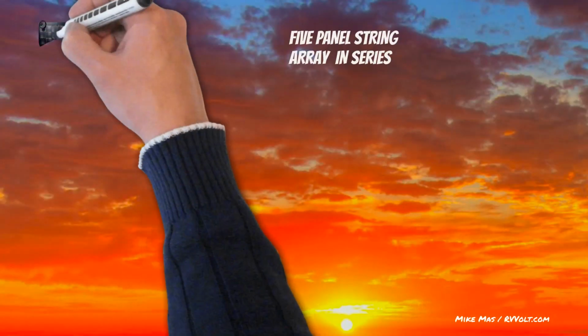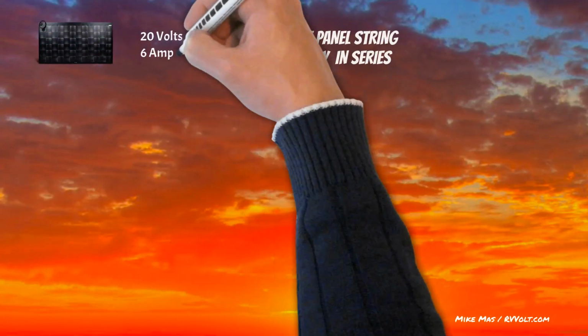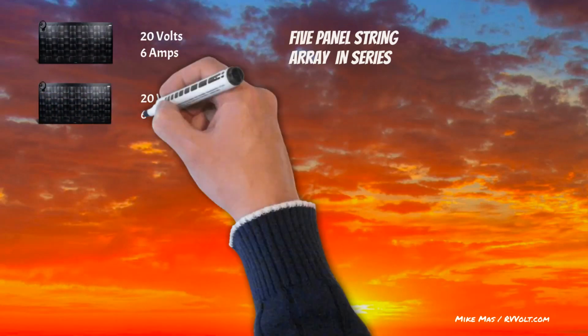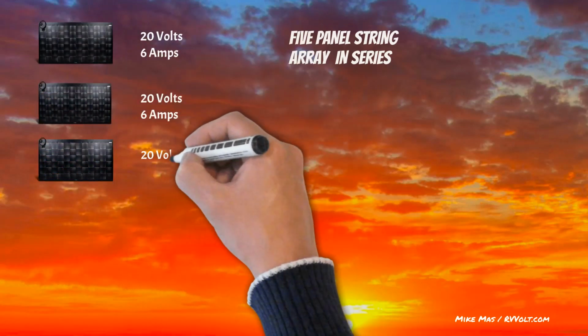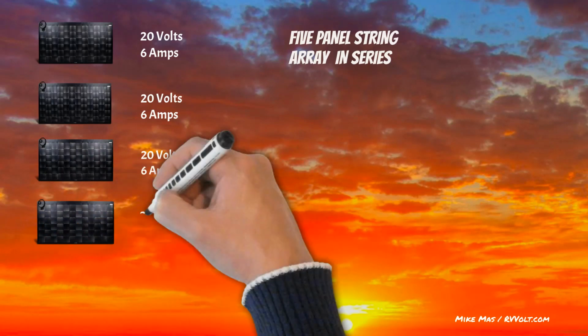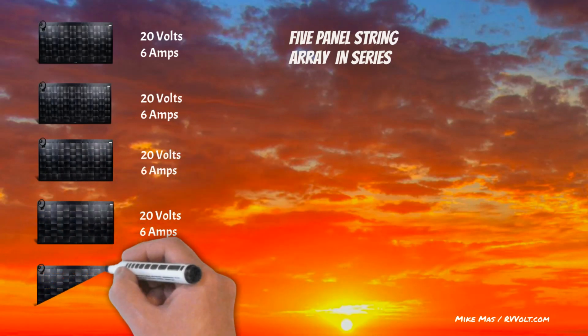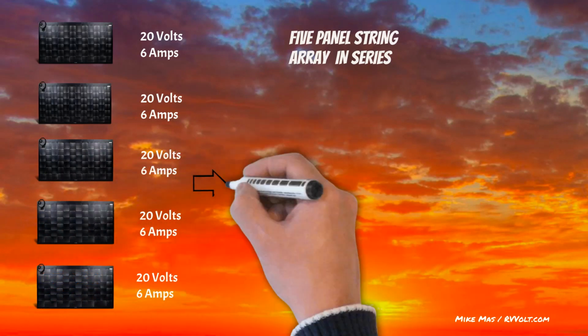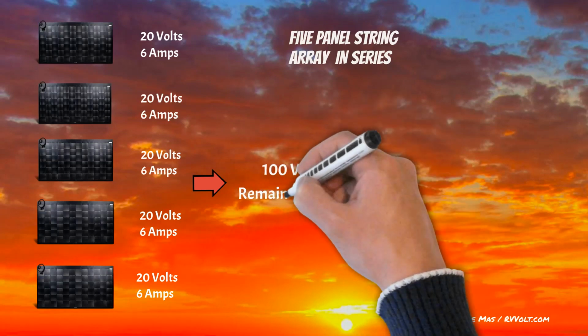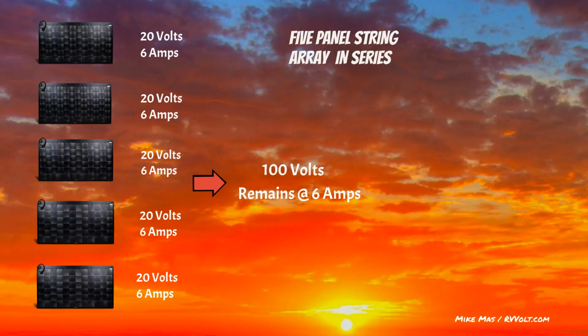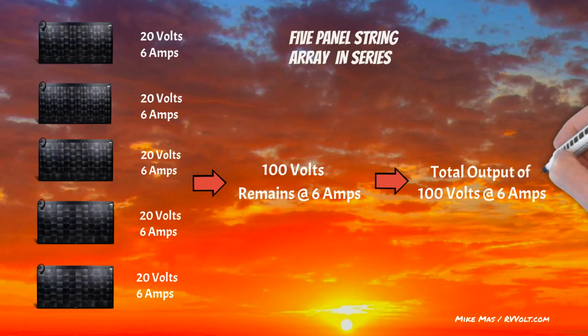As we look at a string of 5 panels in series, we find that each 120-watt panel outputs 20 volts at 6 amps. As we wire our 5 panels in series, the 5 voltages are added together for a total of 100 volts. However, since the panels are in series, the amperage will only equal the value of one panel, or just 6 amps.